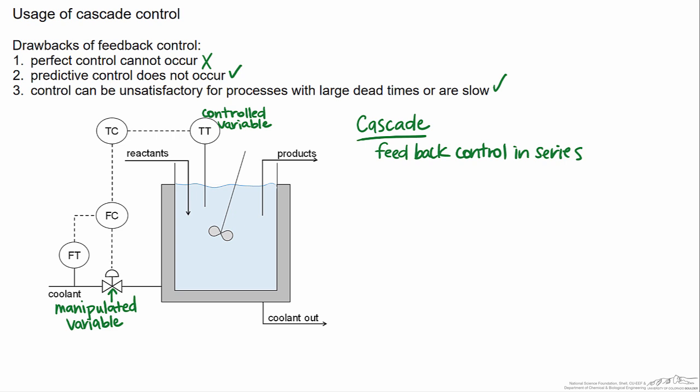The temperature controller does not directly connect to the valve. There is a second layer here where the temperature controller sends its signal to a flow controller, and then the flow controller is also taking information from the flow rate of the coolant. So what it is measuring here is the coolant flow rate, and the flow controller is taking that information in addition to the information from the temperature controller in order to adjust the valve.